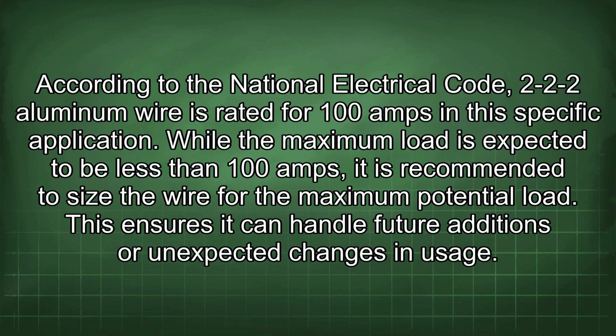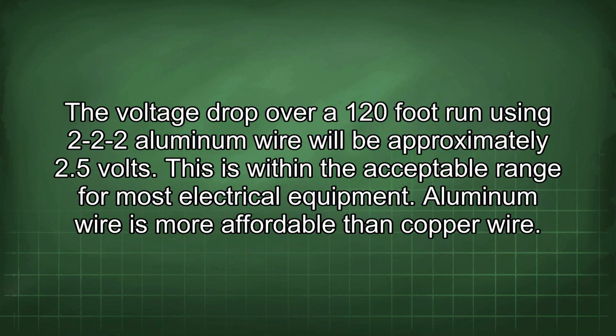According to the National Electrical Code, 2-2-2 aluminum wire is rated for 100 amps in this specific application. While the maximum load is expected to be less than 100 amps, it is recommended to size the wire for the maximum potential load. This ensures it can handle future additions or unexpected changes in usage. The voltage drop over a 120-foot run using 2-2-2 aluminum wire will be approximately 2.5 volts. This is within the acceptable range for most electrical equipment.